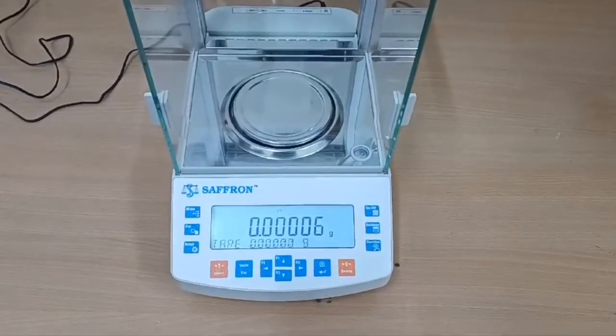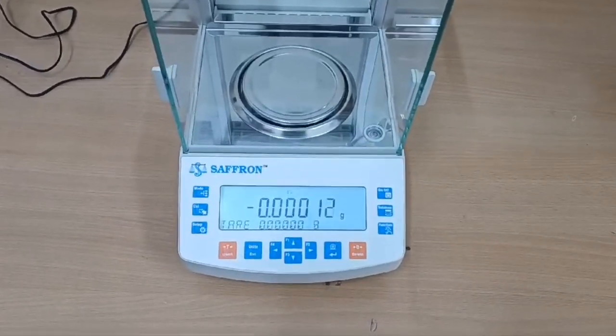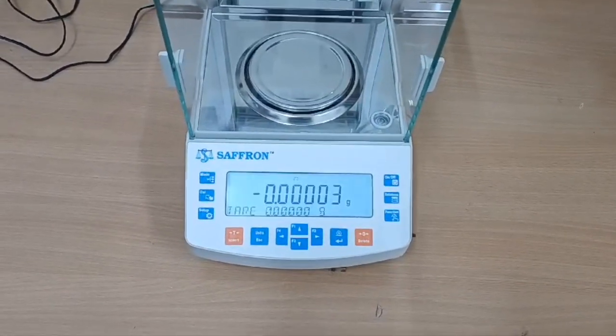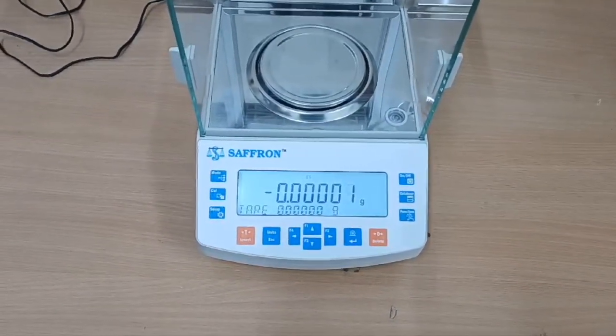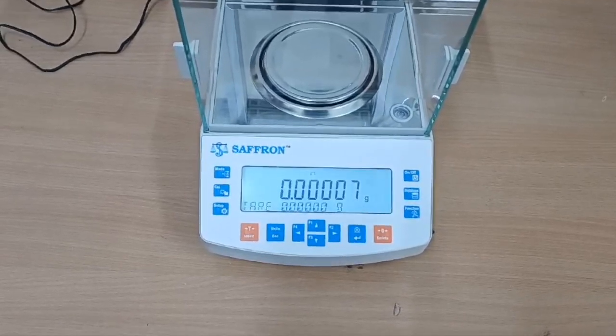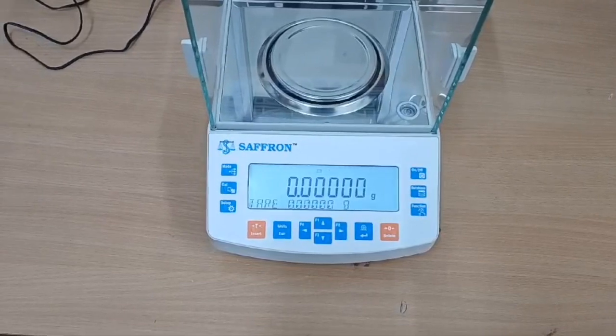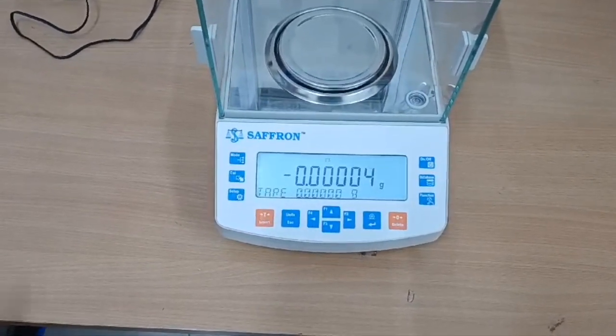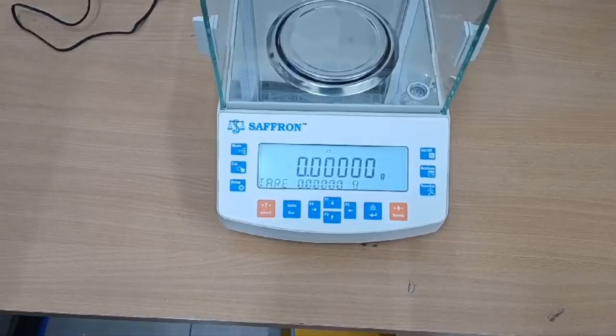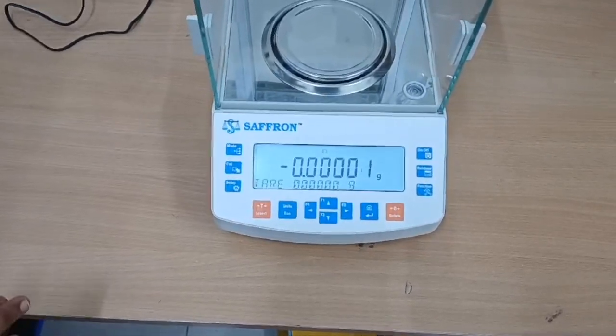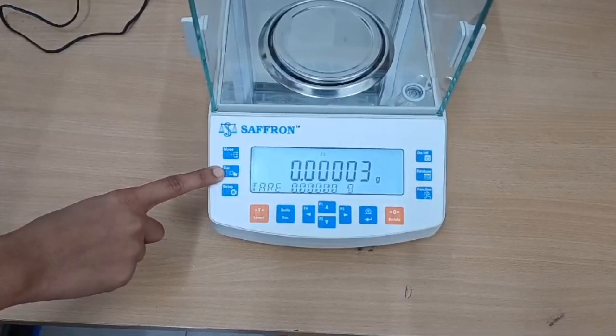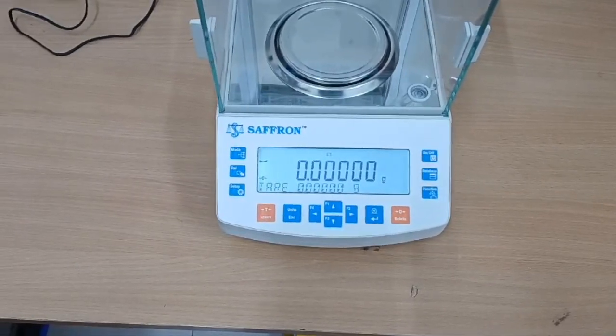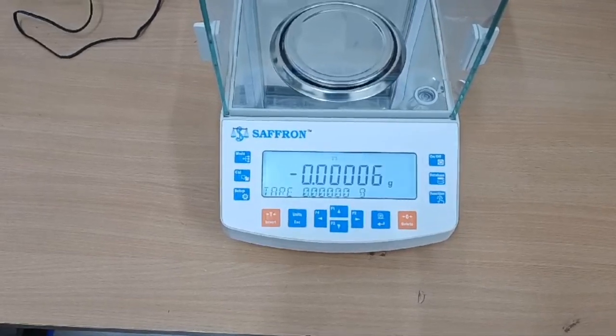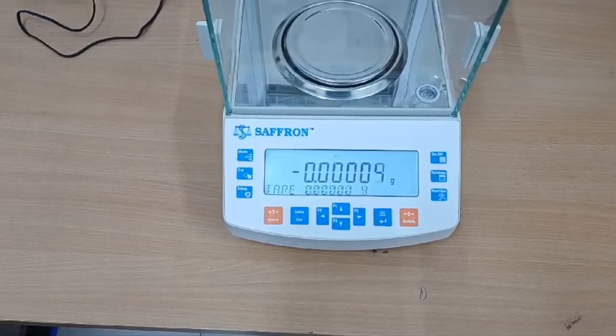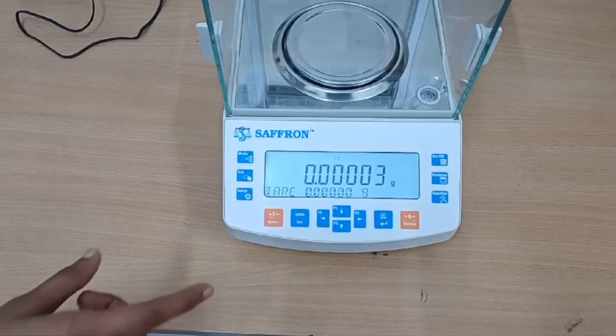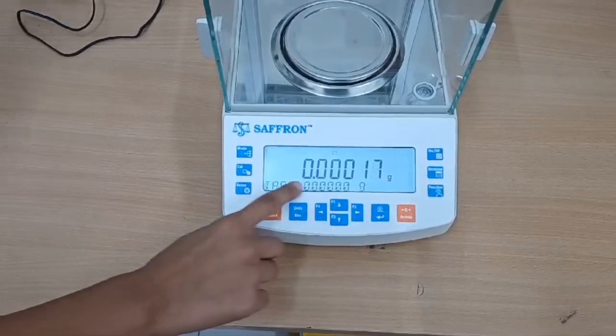Okay, we'll now explain the different aspects of the calibration process. There are different types of calibration. There's internal, external, and user calibration. So the automatic adjustment process is carried out by the instrument itself when it's turned on, and this takes about a minute or two. We'll explain the internal adjustment process, which should be carried out every time you turn on the machine. So once you turn on the instrument, you press the calibration button. The process takes up to 2 to 5 minutes, and during the adjustment process, do not load the weighing pan with any load. The message "do not turn off the calibrator" will appear on the display panel at the bottom.